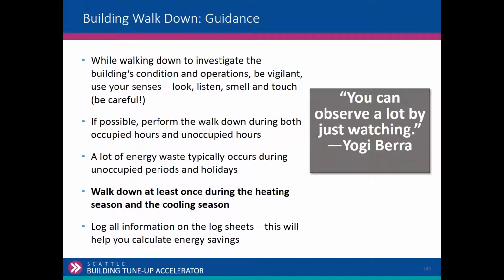Obviously, when you're walking down the building, and this just makes sense, use your senses: look, listen, smell, touch. Does it make sense what you're seeing? It's important to observe the building during different modes of operation. We know that our buildings generally, unless you're a 24/7 building, have an occupied mode and an unoccupied mode. Has anybody done a night walk down or a night walk through? I've always found something on a night walkthrough that could be turned off, or a deficiency, or something to check on a follow-up. So it's good to observe the building both during its unoccupied and its occupied.